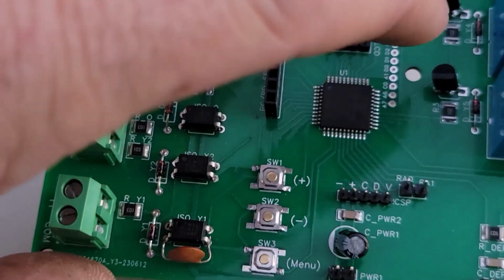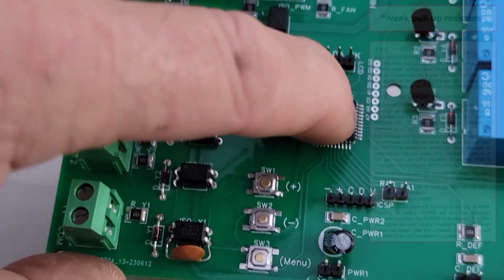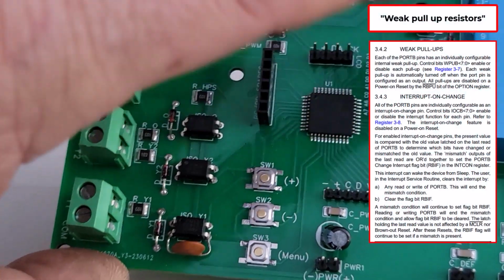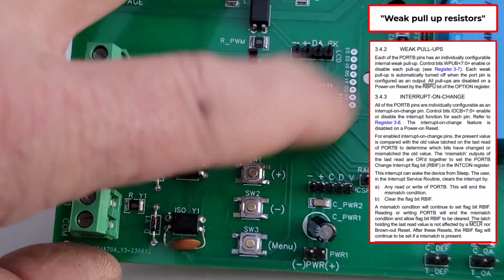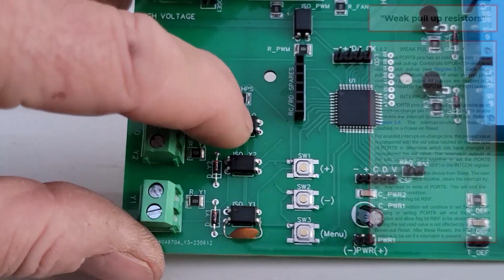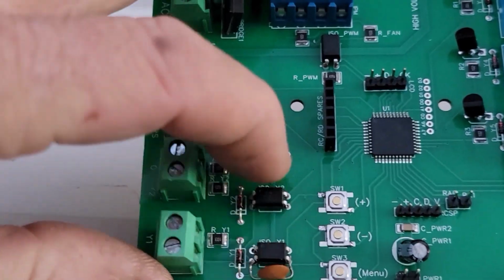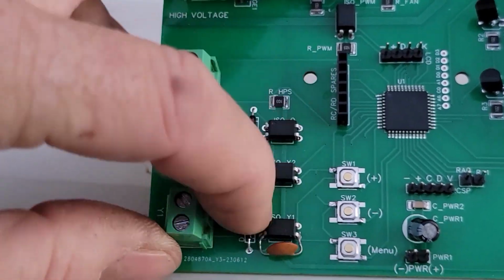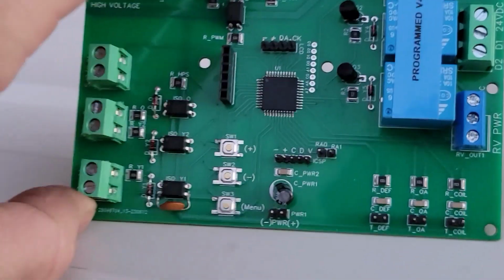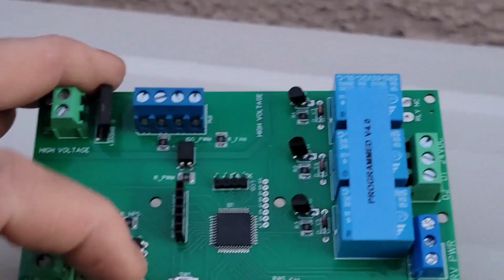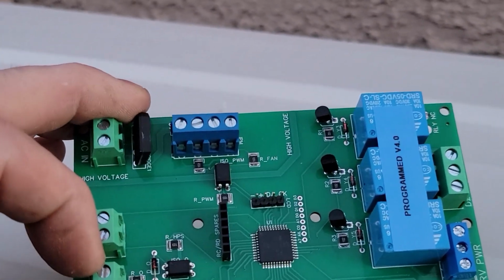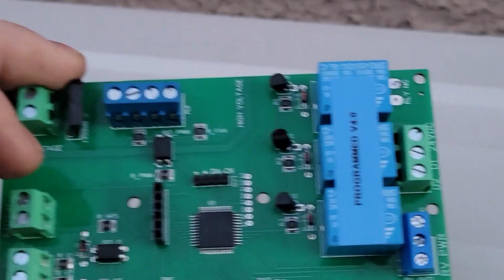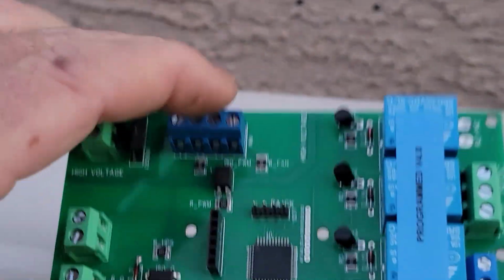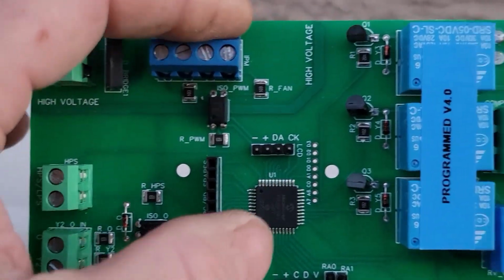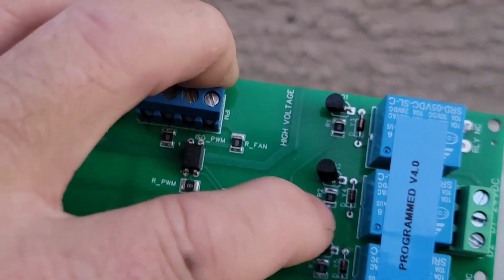Pull up resistors are built into the processor, which you activate in the software in the program. So when one of these goes on, it pulls it down to a logical 0. So in my program, a logical 0 is when it's active from the thermostat. Otherwise, it's a logical 1 by default. You just have to remember that when you're programming it.